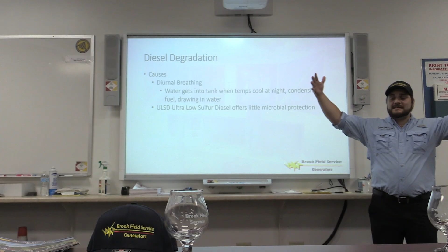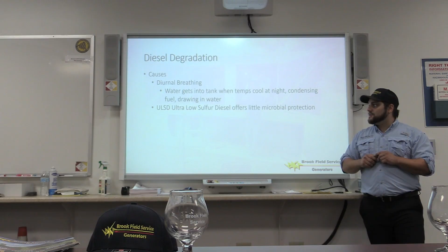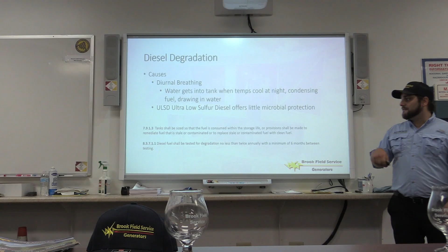Ultra low sulfur diesel offers little microbial protection, as we were talking about with different tiers of environmental protections. The old way was a little better. However, as we're getting into these biofuels and cleaner burning diesel engines, we might see a resurgence of these diesel engines. As we can see here from NFPA 110, tanks will be sized to the fuel consumed within the storage life. Provisions shall be made to remediate any contaminated or stale fuel, and diesel fuel shall be tested for degradation no less than twice annually.